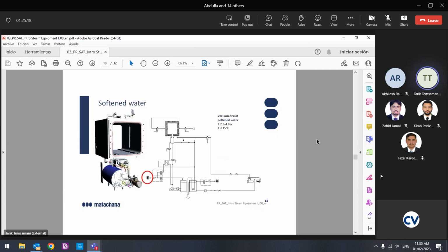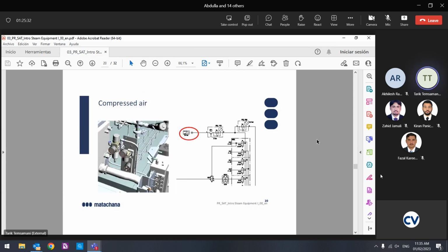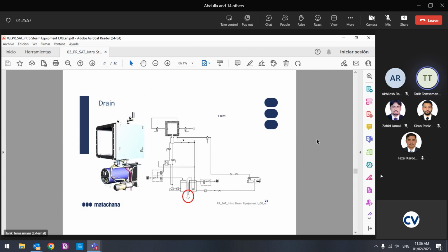Okay, the supply. I told you we need soft water for the vacuum, that's for all the steam machines, and RO water for the liquid. What about the compressed air? We need it. Yes, I saw a small compressor on the S1000. Yeah. Normally it's optional, but sometimes it can be integrated with the machine. If it's not coming with the machine, then we need the air supply from the hospital. 7 bar? 5 to 7.